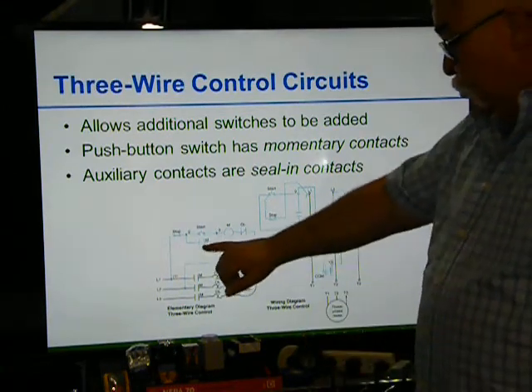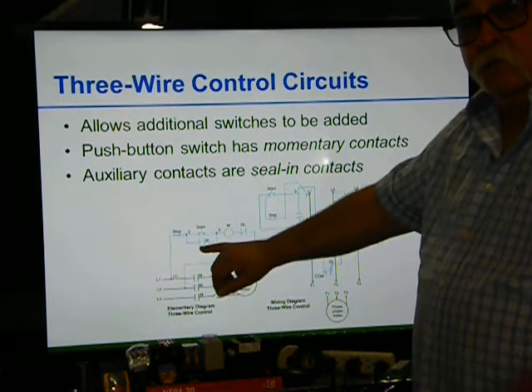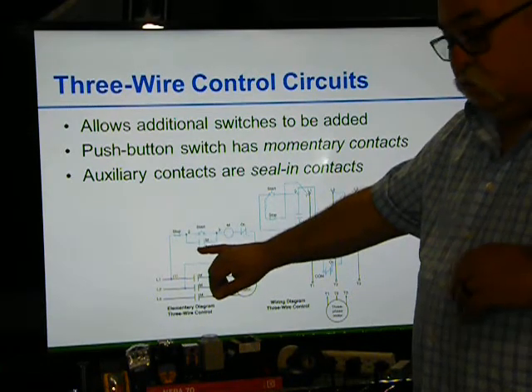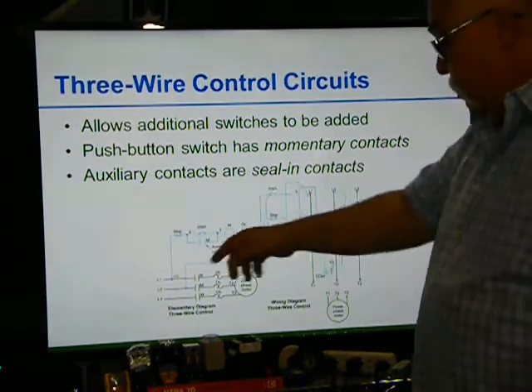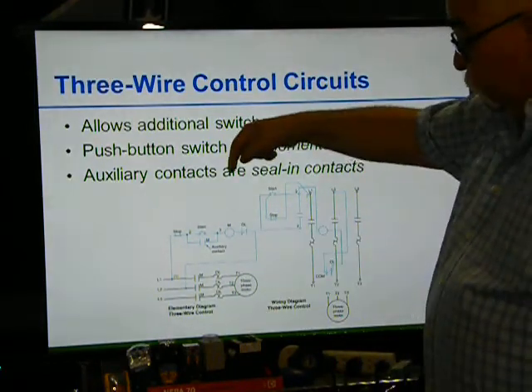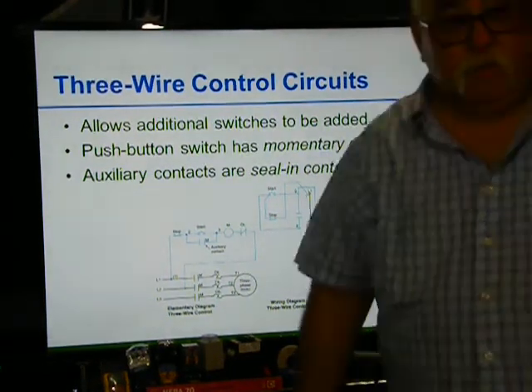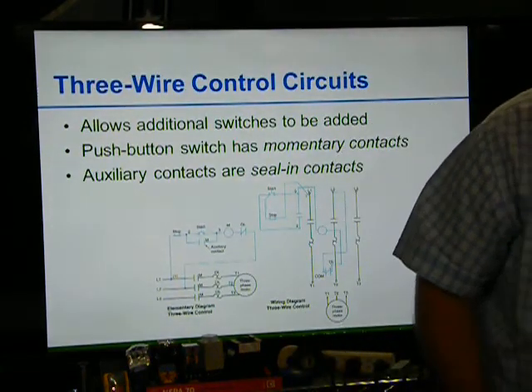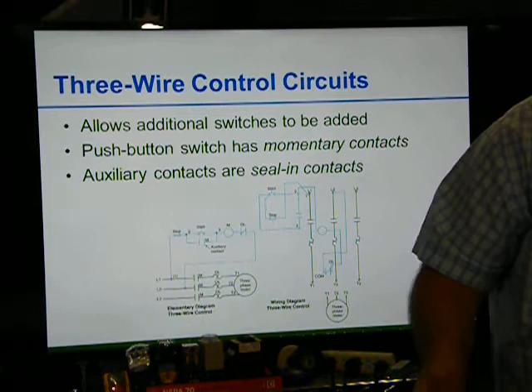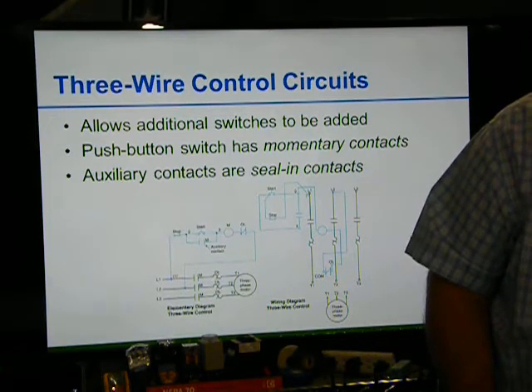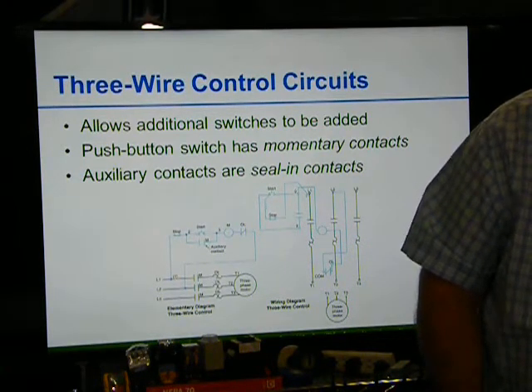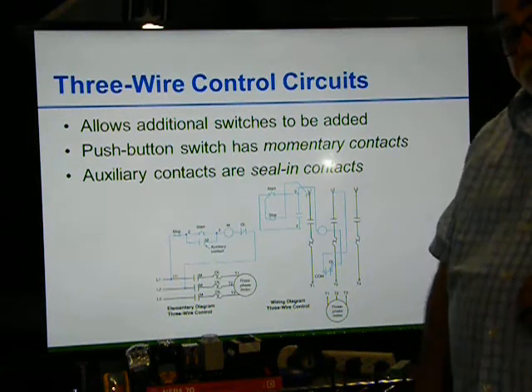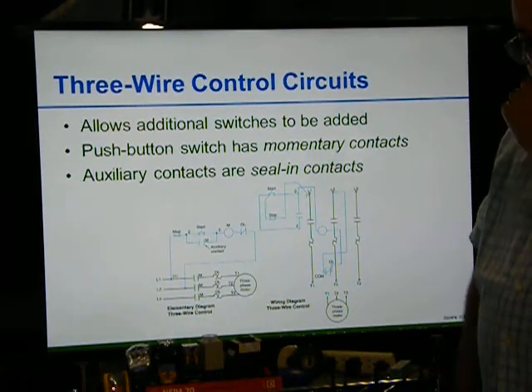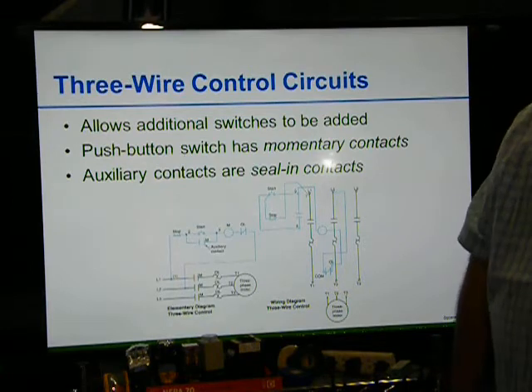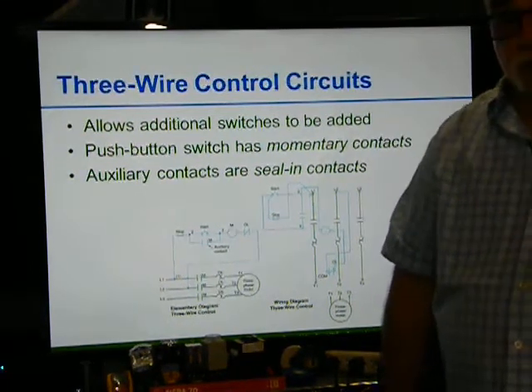Again, once this auxiliary contact loses power, it turns off. So there's no way that power comes across. So the only way you're going to be able to turn it back on is by pushing the start. So if the power is interrupted on a 3-wire circuit, it does not automatically restart the motor when the power is restored. A 3-wire circuit also provides low voltage protection. One of the questions in assignment number 2 was, what doesn't a 2-wire do? It doesn't provide you low voltage protection.